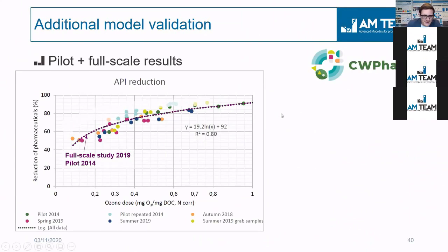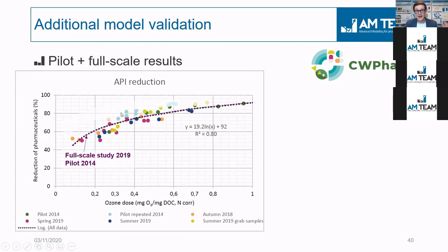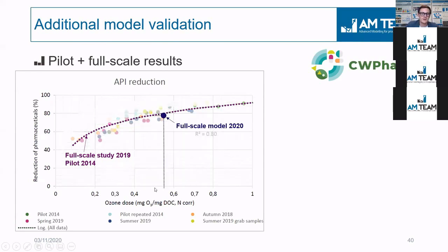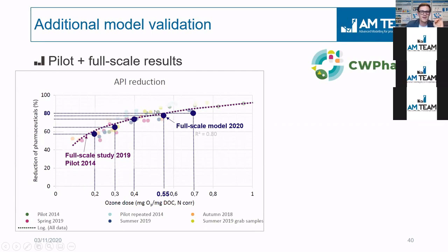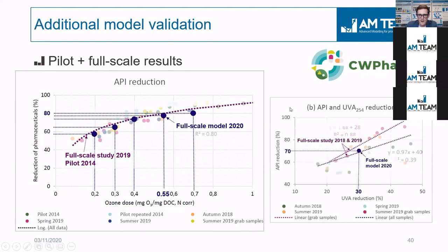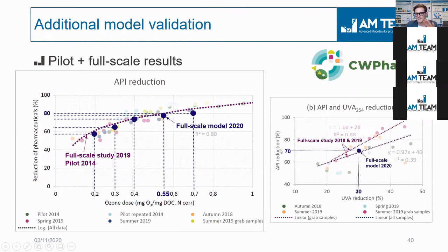So what we have done here is also some validation, additional validation, we have looked at what pilots and full-scale studies set in reality, compared to what our model set in reality. So this is the reduction of pharmaceuticals as function of the ozone dose, DOC-based. You can see that our model is nicely capturing the trend, which are the dark blue dots here. You can see that the same pattern is more or less happening. This is the average removal of eight pharmaceuticals. Okay, so average, on average, for example, with a 0.55 dose, you have around 80% average removal. You can also do the same with reduction of UVA, where we controlled the plant in our model at 30%. And we observed more or less 70% average reduction, which was very much in line also with both the full-scale and pilot runs.